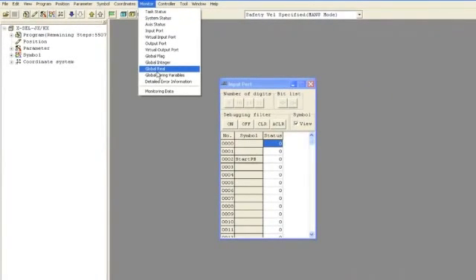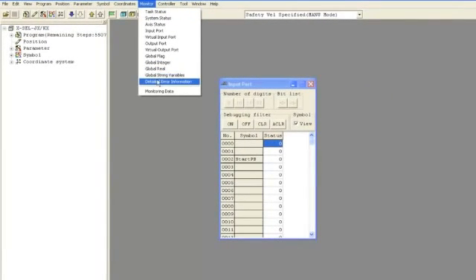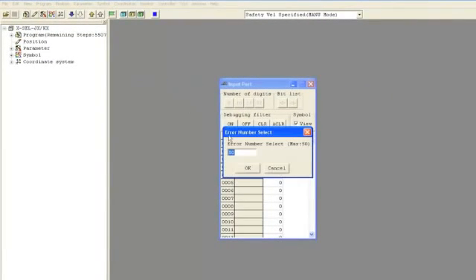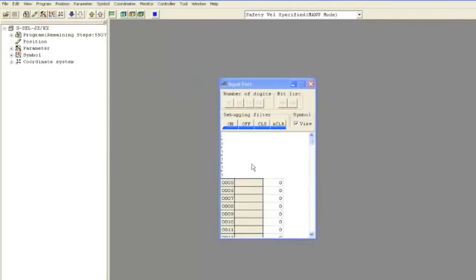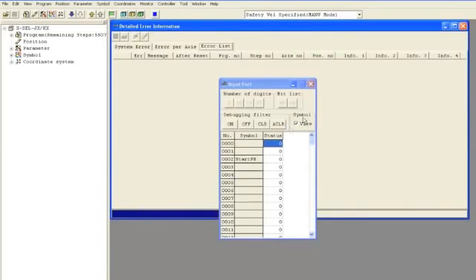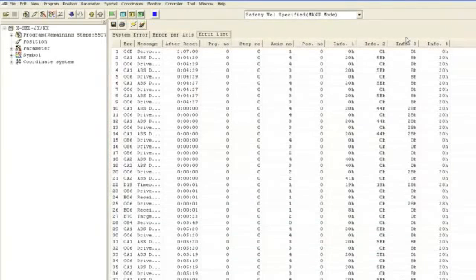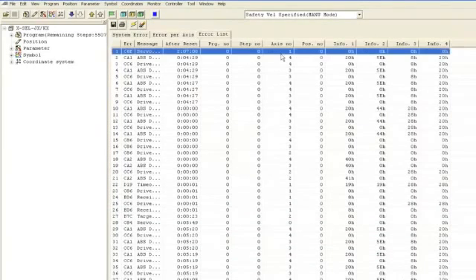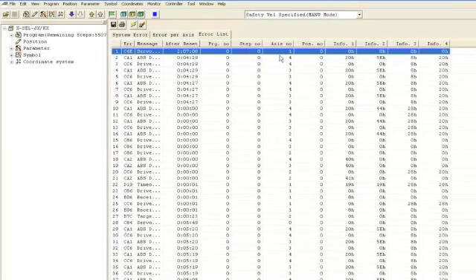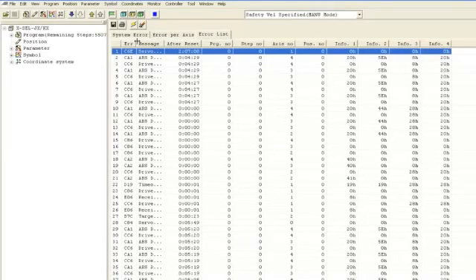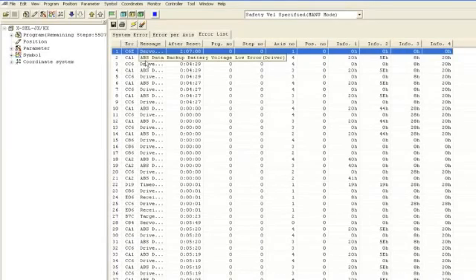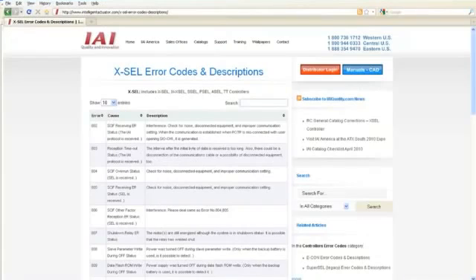Also from the monitor window, you can look at the detailed error information. The detailed error information stores all of the detailed errors with error codes, if it happened on a particular program, the step number of the program, the particular axis it happened on, as well as the 3-letter or 3-digit code for the error message. You can use this 3-digit error code to look up the error inside the IAI programming manual as well as on the IAI website.